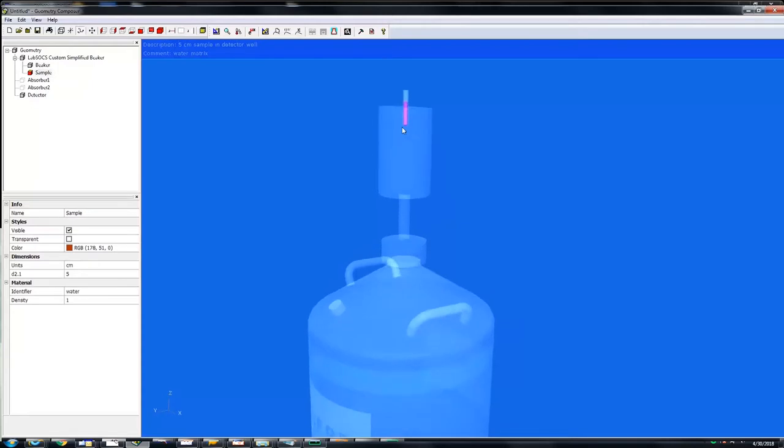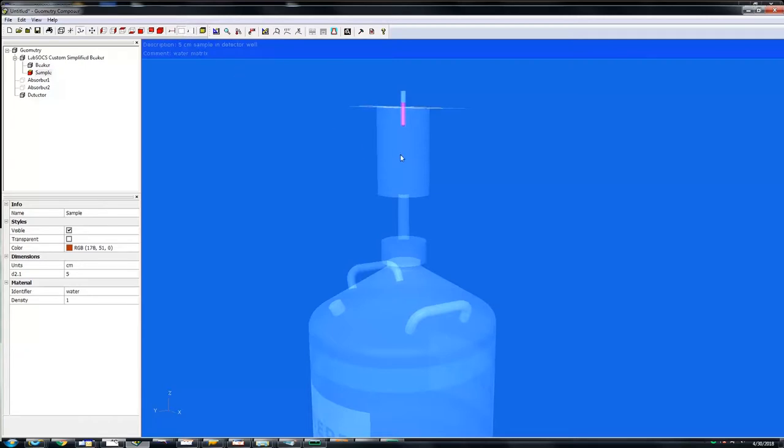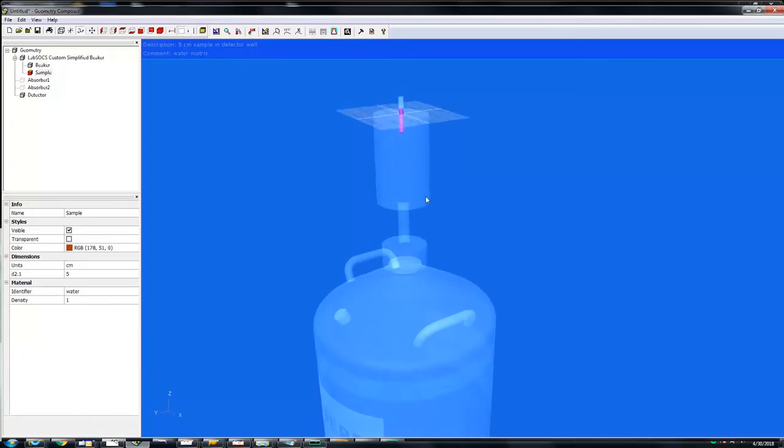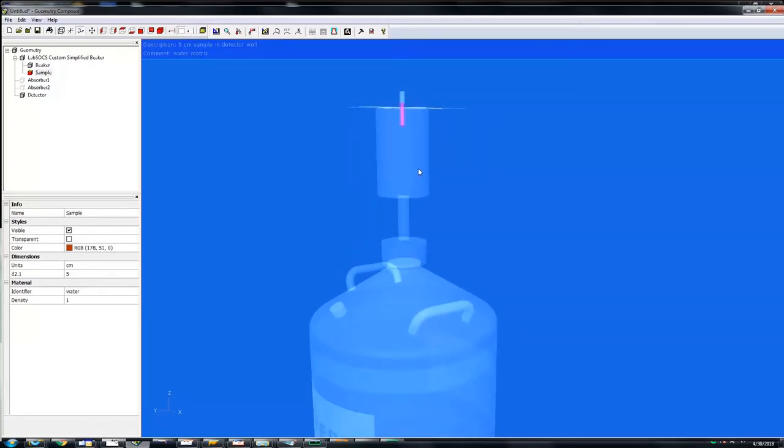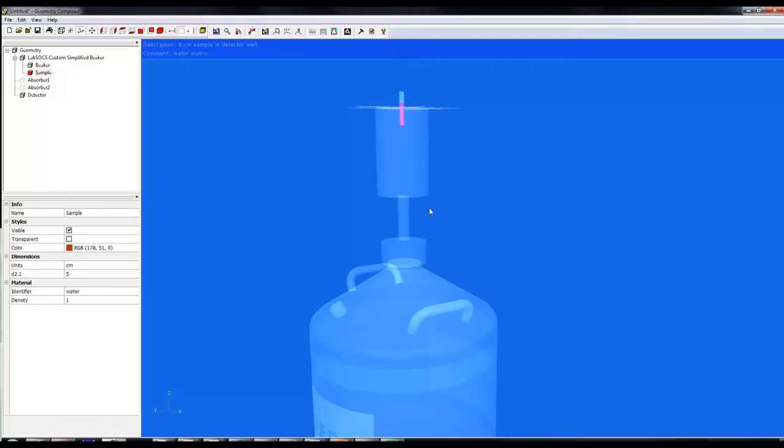Put on the reference plane for more accuracy to see if the sample is above or below the detector. You want to go ahead and make this flat. This shows that our current sample is exceeding the well. If your physical sample does not exceed the well of the detector, this could be an indicator that the measured fill height was incorrect.